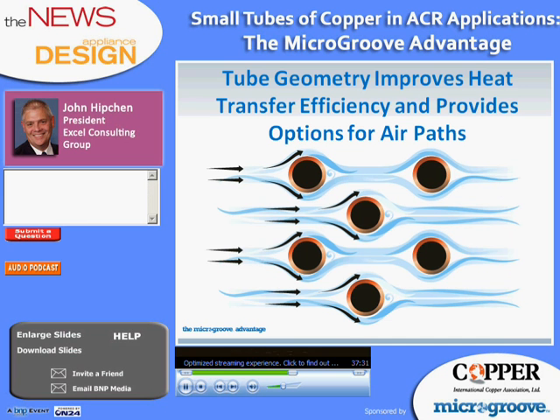Comparison studies often cite a high airside pressure drop as a disadvantage for copper tubes, but we must remember that both the tube geometry and the fin design are responsible for the airside pressure drop. With copper tubes, there are a number of options, such as the number of tubes, how the tubes are arranged, or the tube geometry, and lastly, all the parameters that go into the fins, such as the fin pitch, louvers, louver angles, etc. Microchannel tubes allow only one path for air, and therefore the only parameters that are left to deal with airflow and the airside pressure drop are those related to fin design.